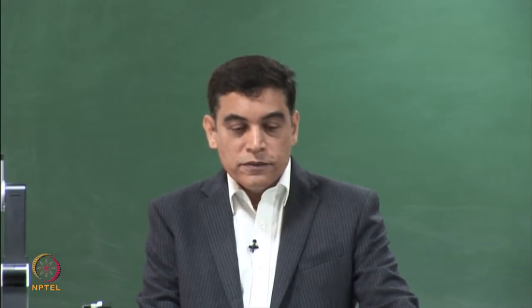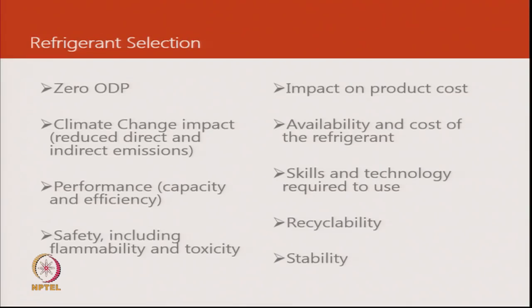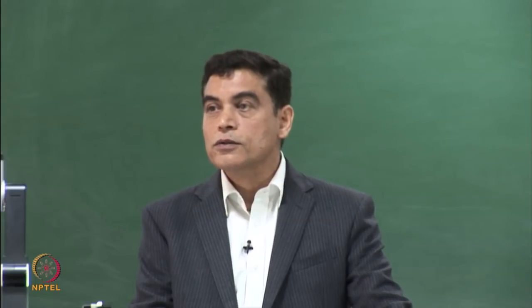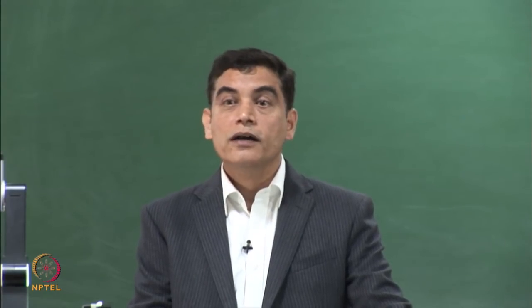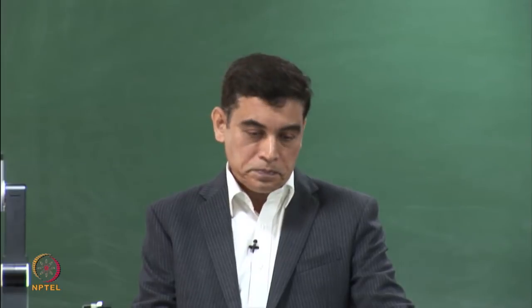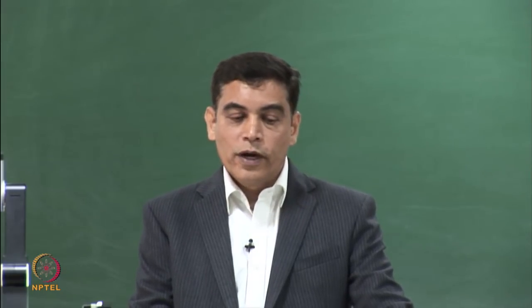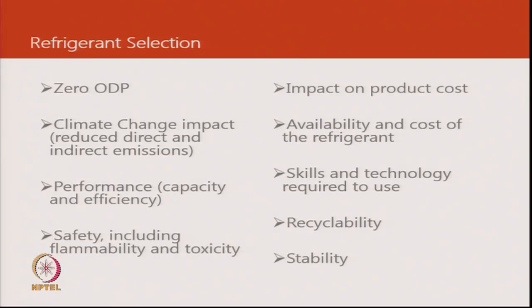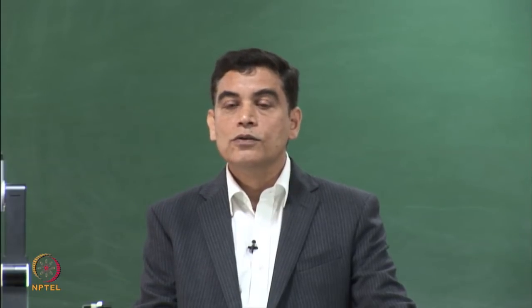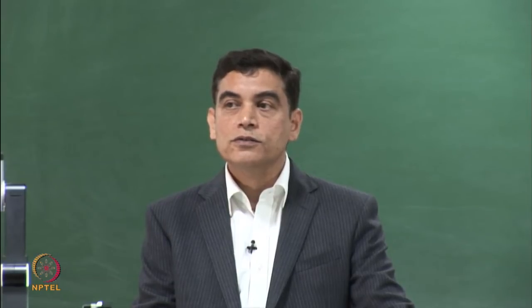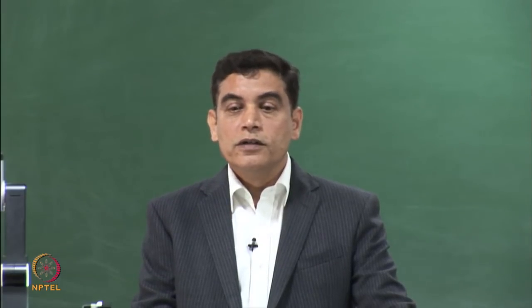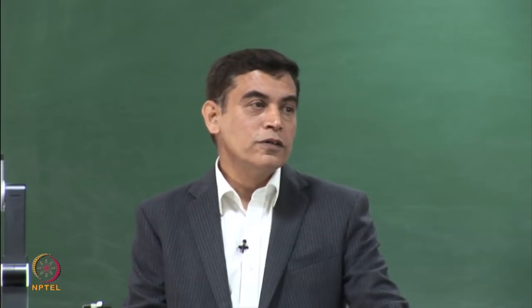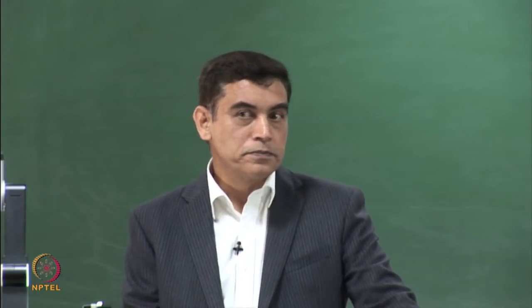Then continuing on with the refrigerant selection parameters, the newer one is 0 ODP. Today, if you are designing equipment, we will not look for anything which has an ozone depleting potential. So, R22 is something not to be considered anymore, R12 is not to be considered anymore, though they are ideal refrigerants from a thermodynamic perspective. And then we will look at climate change impact. There is no agreement globally yet, but there is concern, and there are guidelines to look for lower global warming potential refrigerants. If everything is equal for two different refrigerants, we will go for the refrigerant which has a lower global warming potential.